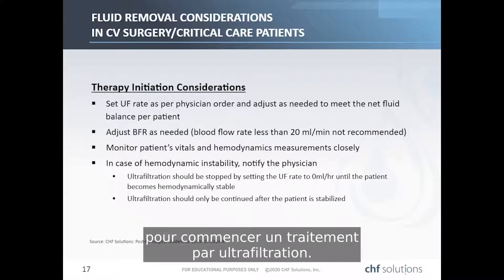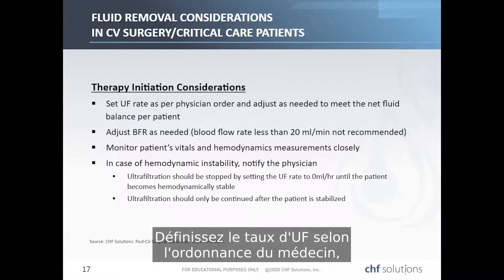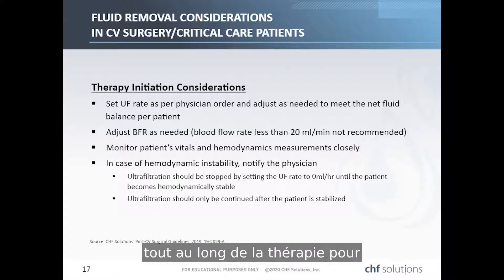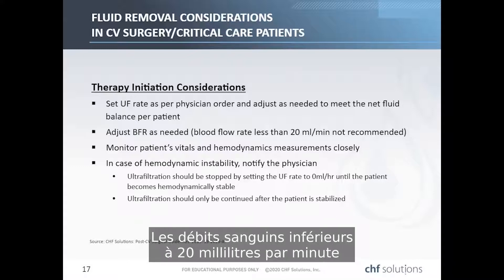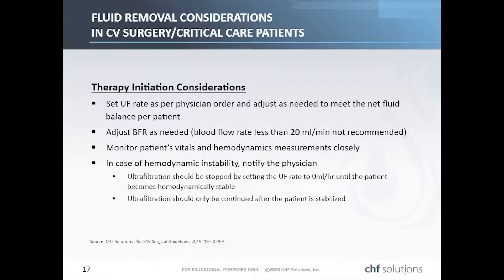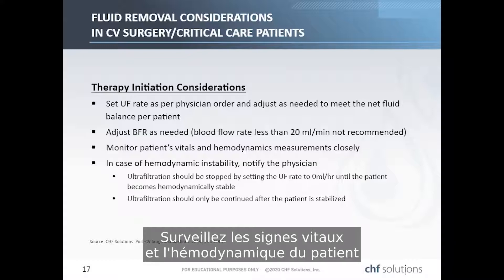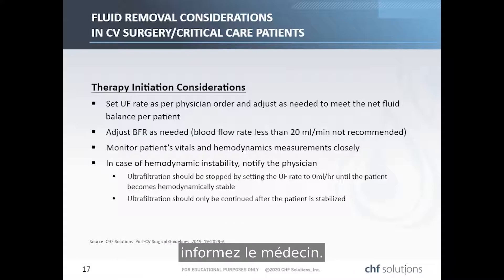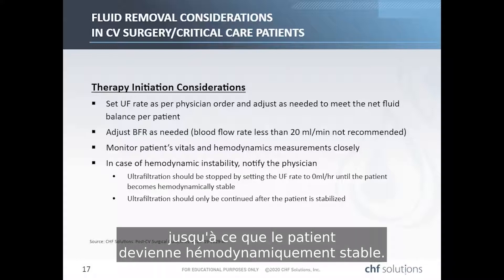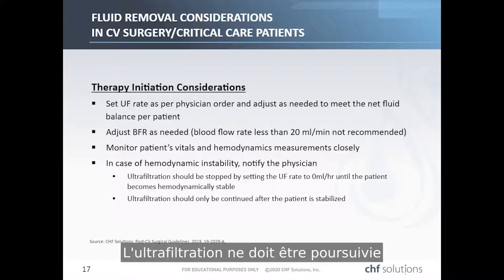When initiating ultrafiltration therapy, set the UF rate per physician order, adjusting as needed throughout therapy. Adjust the blood flow rate as needed; blood flow rates below 20 mL per minute are not recommended. Monitor the patient's vital signs and hemodynamics. In the case of hemodynamic instability, notify the physician. Ultrafiltration may need to be stopped by setting the UF rate to zero until the patient becomes hemodynamically stable, and should only be continued after stabilization.